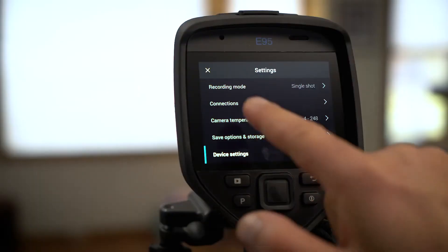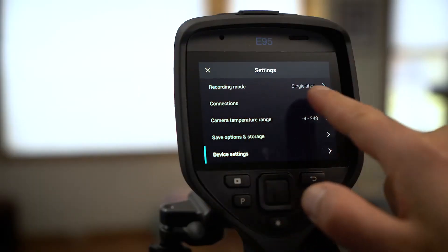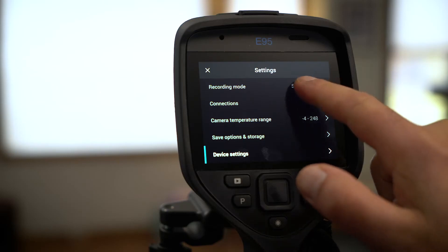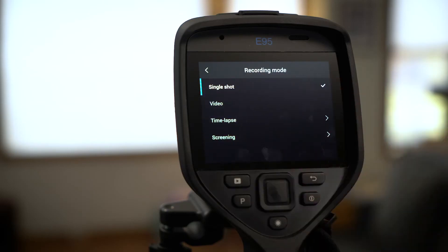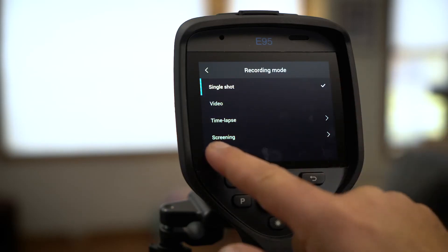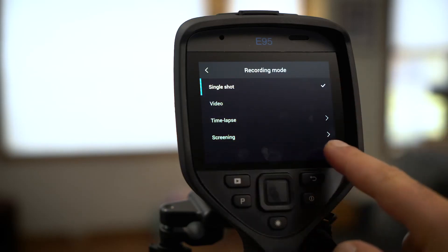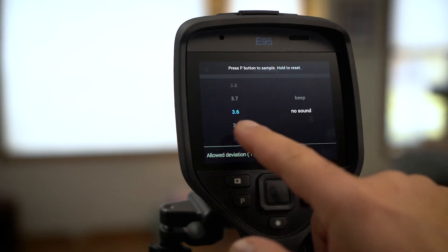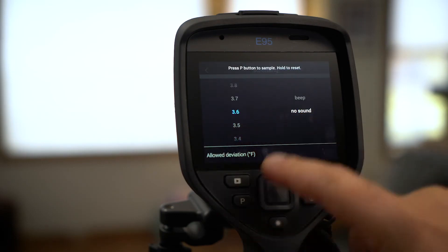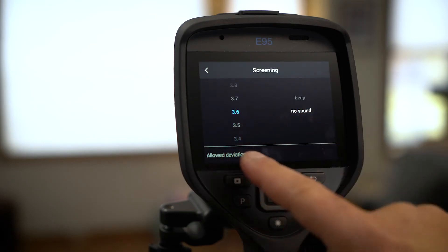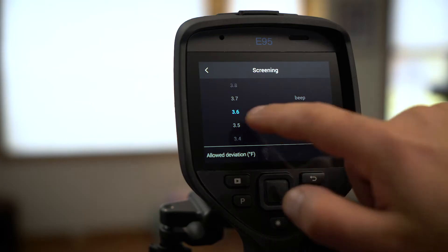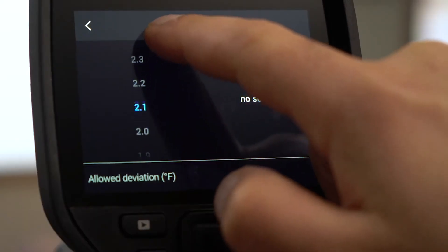Now we need to set the imaging mode to Screening. Select Screening. Here's where you can set your alarm threshold. We're in degrees Fahrenheit, so we'll set the threshold to 2 degrees.